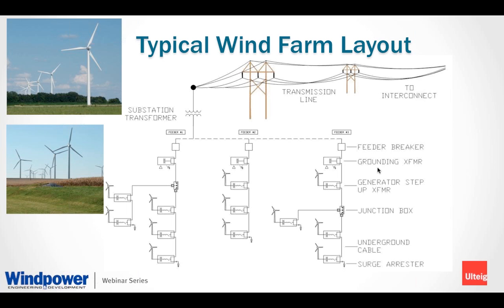Going down further, the substation has 3 feeder breakers in this example. These feeder breakers help protect the wind farm for the 34.5 kV collection feeders. Each feeder breaker contains an effectively grounded system device, typically. This can be either a grounding transformer or a grounding breaker.